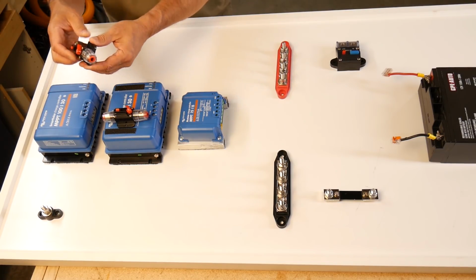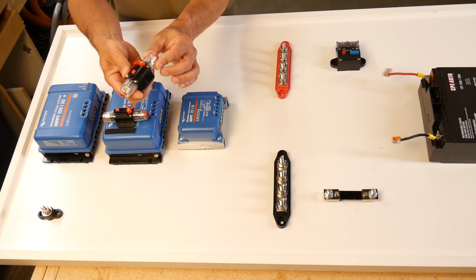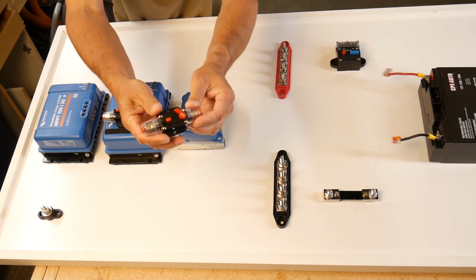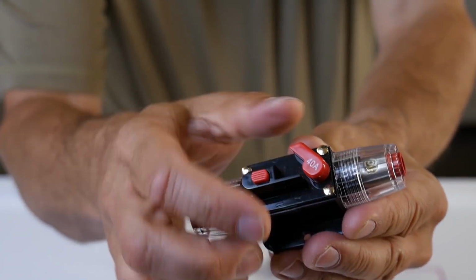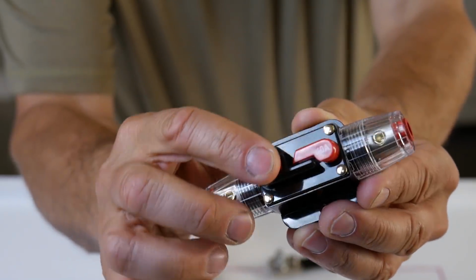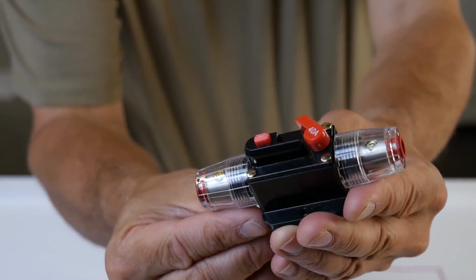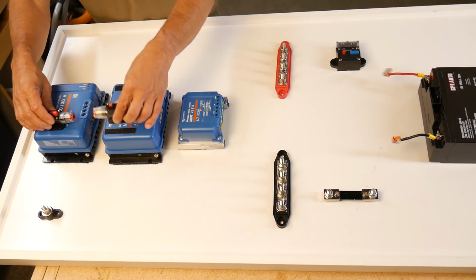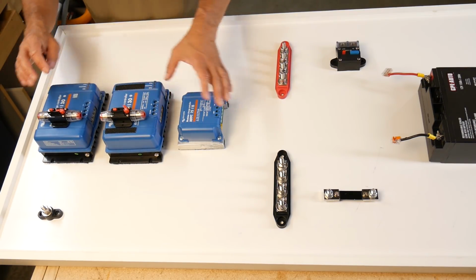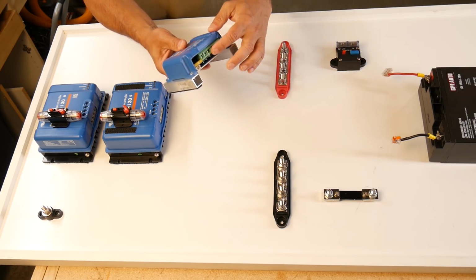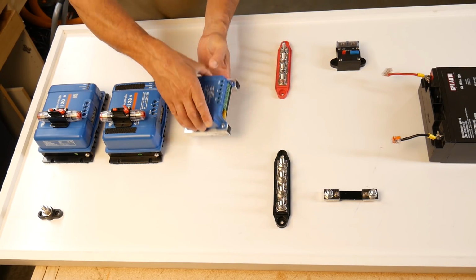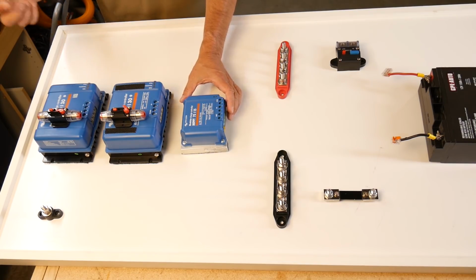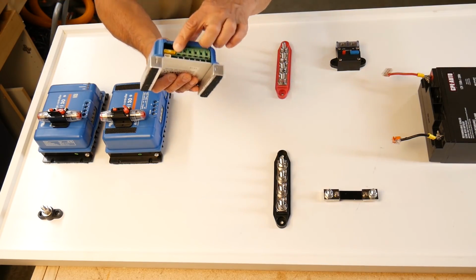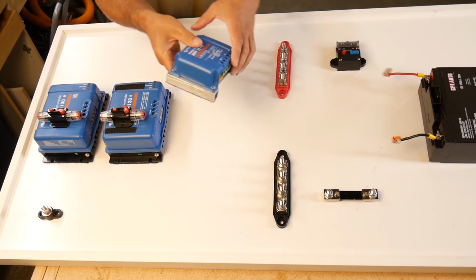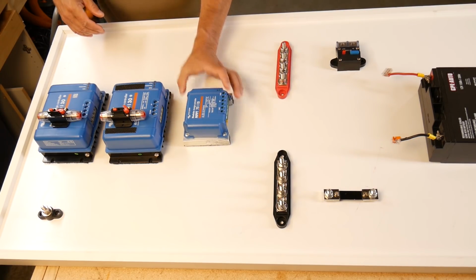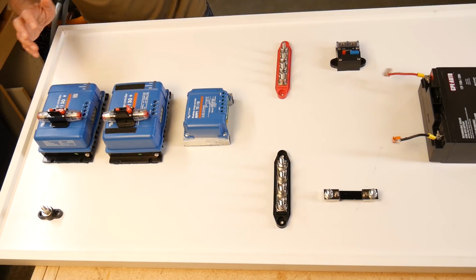Coming into the charge controller, the main arrays are going to go through circuit breakers — each one will have a circuit breaker that also doubles as a cutoff switch, one for each of these on the inputs. The smaller controller doesn't really need one since I already have a switch in line with the input for that plug, and this controller also has a small fuse in it, so it won't need the circuit breaker. I'll just leave those there so you have an idea.